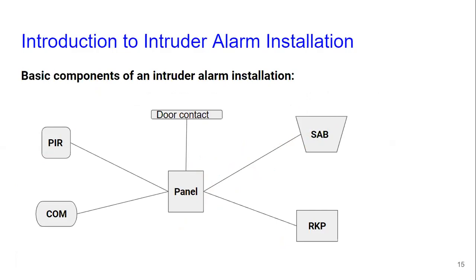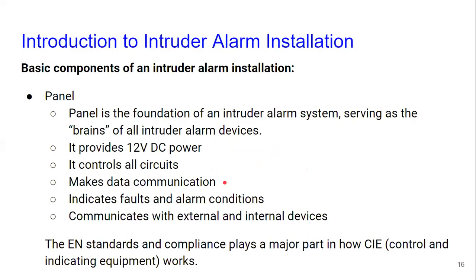There are different ways to wire — you can do bus network, and some systems like Risco give different wiring options. For a small domestic installation, you decide where the panel goes and run cable from every sensor to the panel in a star-type wiring. The panel provides power to all devices — power is centralized. It controls all circuits, makes data communication with devices like keypads and expanders, and indicates any faults via LEDs and LCDs.